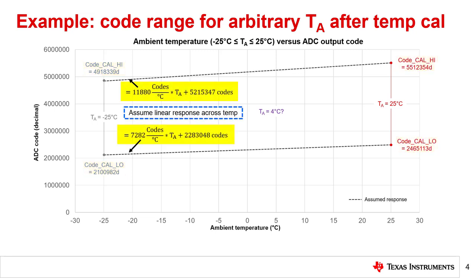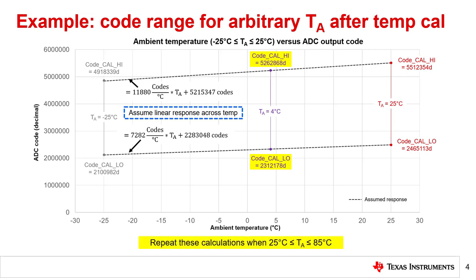Next, using the assumption that the transfer function has a linear relationship with respect to temperature, calculate the equation for the line connecting code cal high and code cal low for each calibrated temperature as shown. Finally, use these equations to calculate the transfer function's code range at any ambient temperature between the calibrated values. Using the values provided, code cal high and code cal low at 4 degrees Celsius are shown on the plot in purple. Note that this process would need to be repeated for any additional sets of adjacent calibration codes, which would be 25 and 85 degrees Celsius in this example.